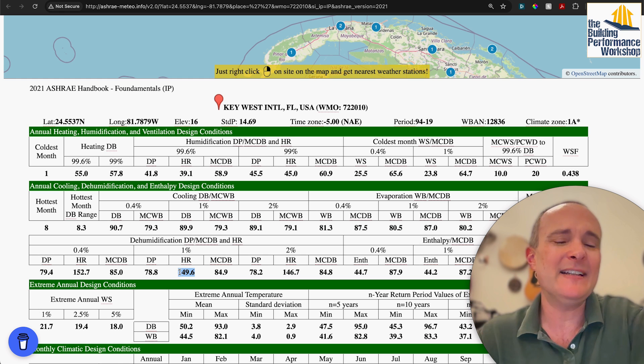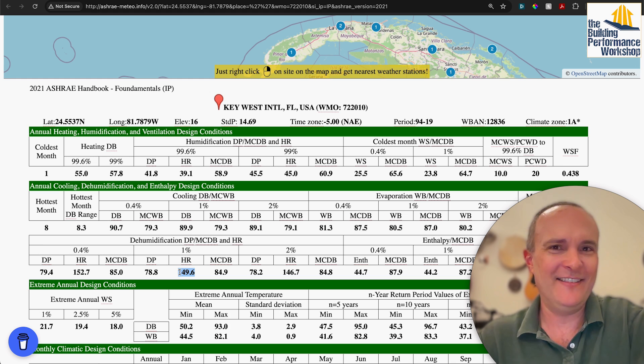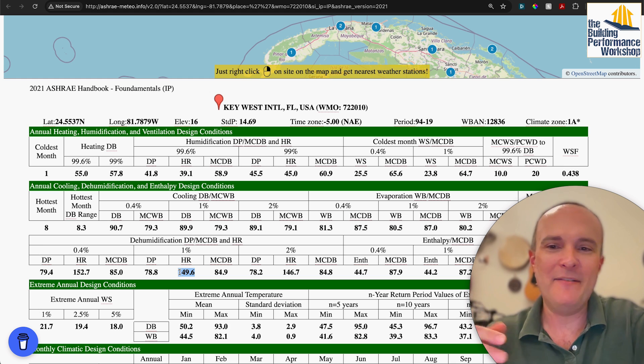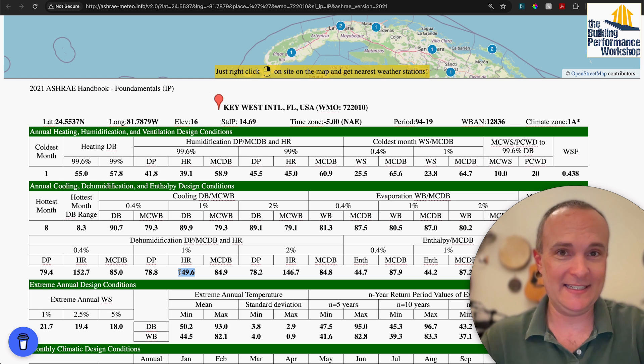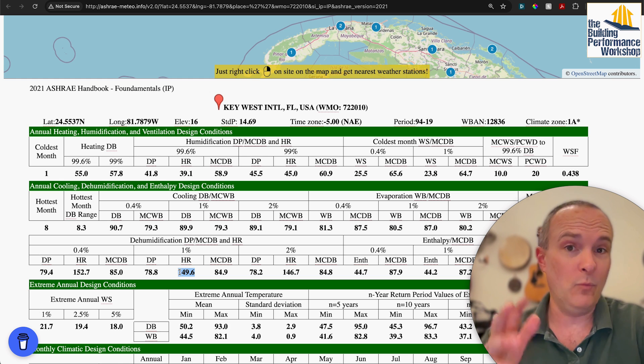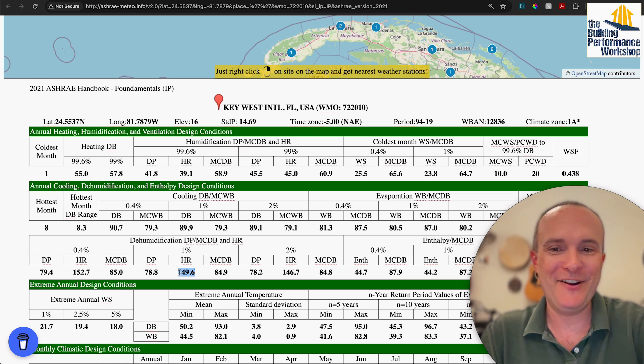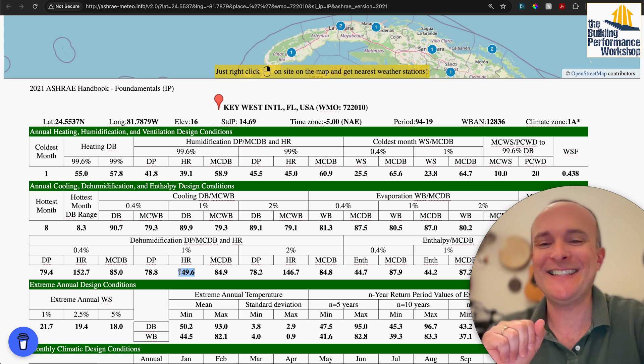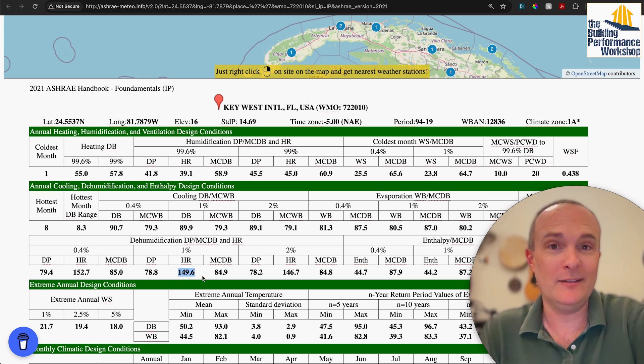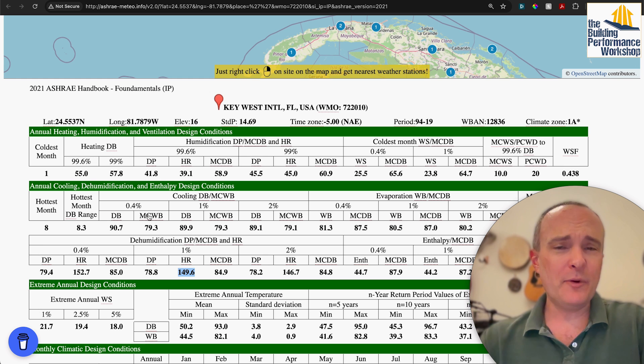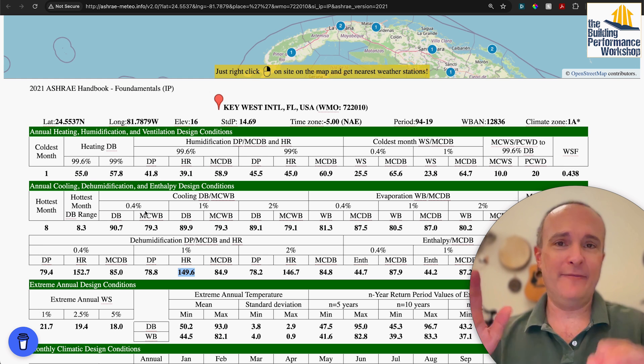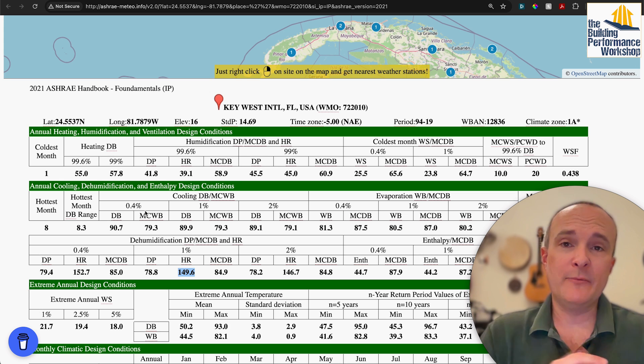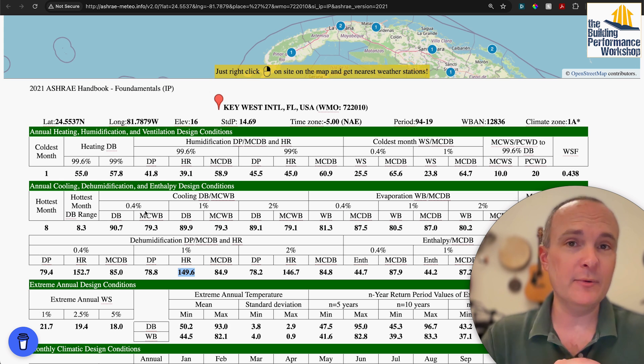The humidity ratio here is 150 grains per pound — basically the highest we see in the United States. You can get up to 160, but that's about as wet as it gets domestically. There are other places in the world with more moisture, but that's not what this video is about. Those are the three basic data points we take out of this table to solve humidity and comfort-related problems.